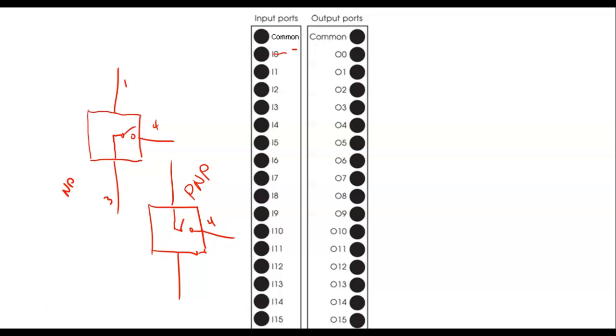So you go out and say, well, I need an inductive sensor, and you go into your stock room and you find one and say, well, this is about the same. I'm going to go out there and hook it up, and you hook it up and the dang thing don't work. And you say, well, this must be bad too. Then you go back and do another one. It's bad. I've seen people go through like 3 sensors and they think they're all bad. But they what? Yeah, they just picked the wrong one. They knew it was an inductive sensor, but they picked the wrong one.